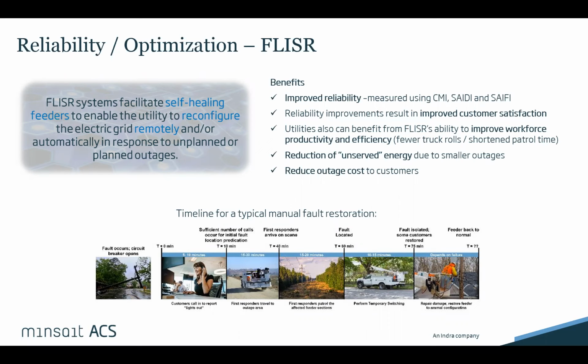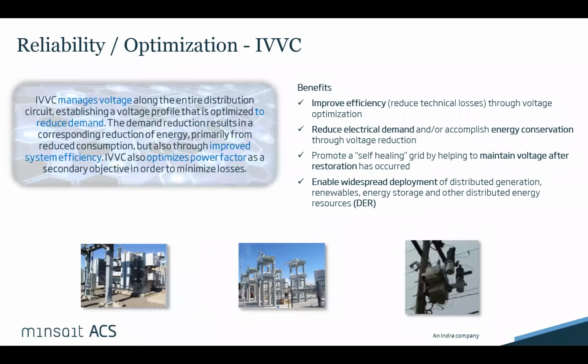So at the bottom you see a typical timeline for a manual fault restoration without automation, where the fault might take in excess of an hour to locate, isolate, and then provide partial restoration in response to a fault. Whereas with FLISR deployed on the system, that isolation and partial restoration can be complete in a minute or less. And of course, the key there being, as long as we keep that under 5 minutes, we've kept that particular outage from being a sustained outage that's reported in our performance indices. So FLISR can have a significant impact, particularly on more problematic areas of the utility network.